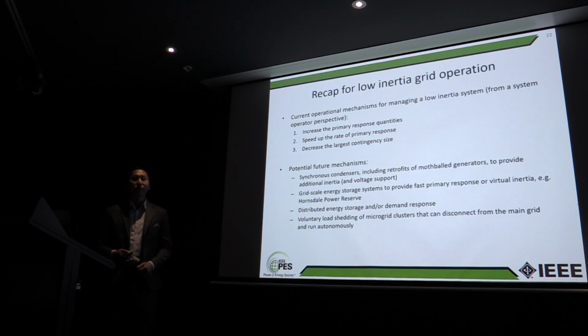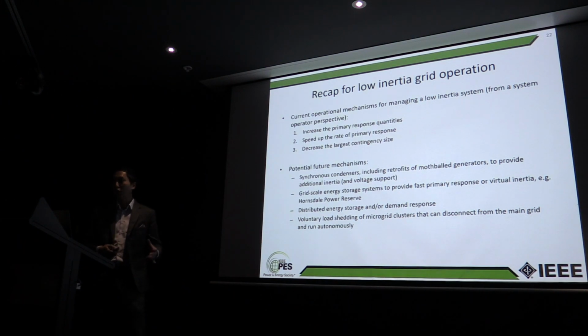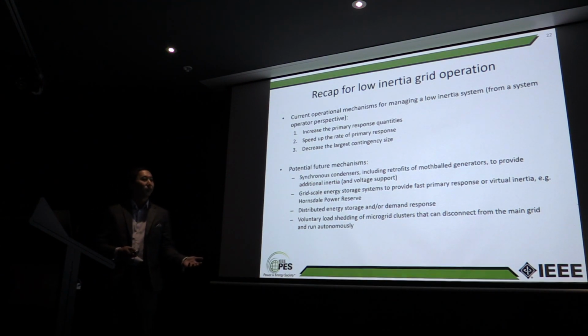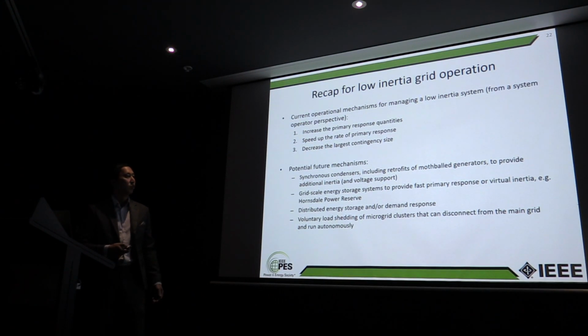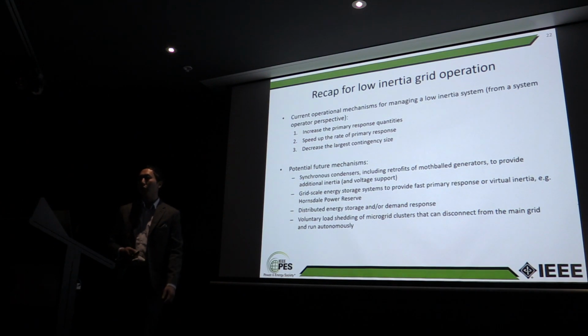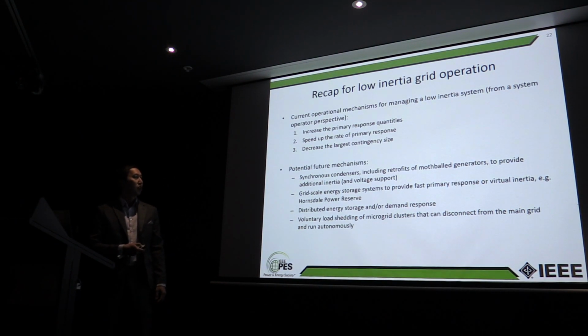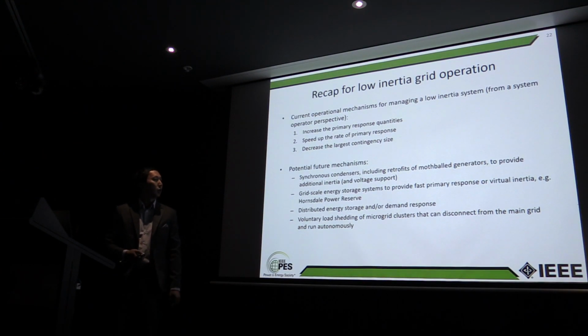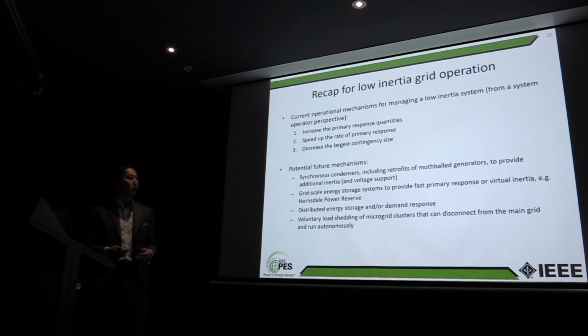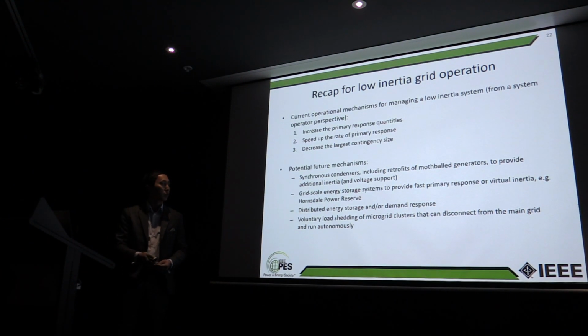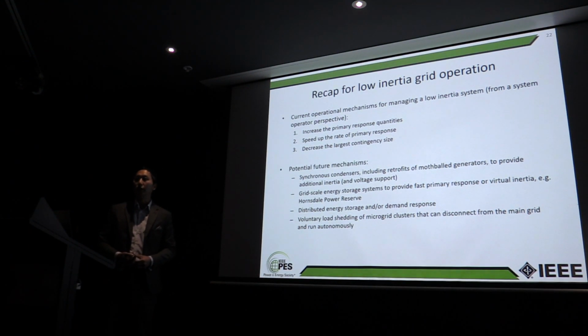But going into the future, what can we do? These are more technological options as they unfold over time. We can add condensers into the system, which are basically synchronous machines that have no load or generation connected to them, prime movers, I mean. And that could be simply a retrofit of an existing mothball generator. That's possible. And that provides inertia and also provides voltage support, which is nice. You could have grid-scale energy storage systems that provide this virtual inertia or the fast frequency response, which is essentially what the Hornsdale Power Reserve in South Australia is, among other things.